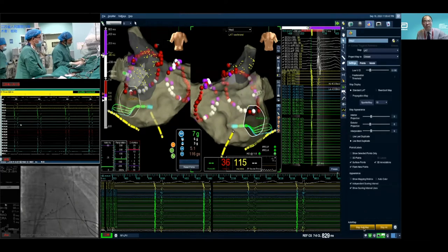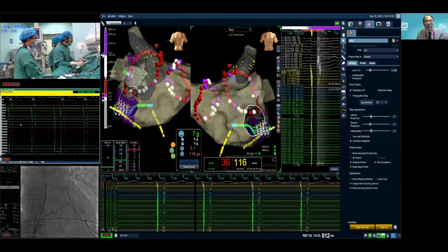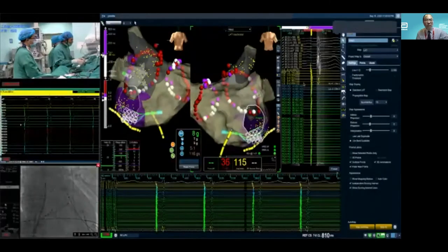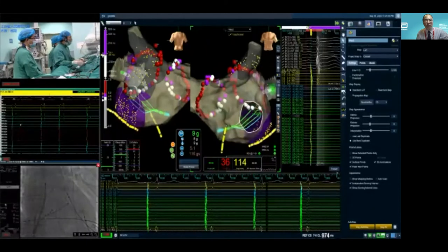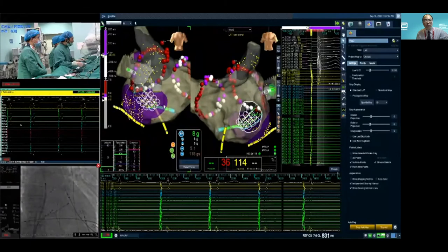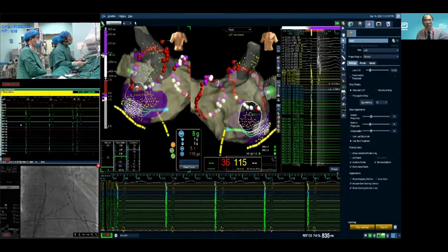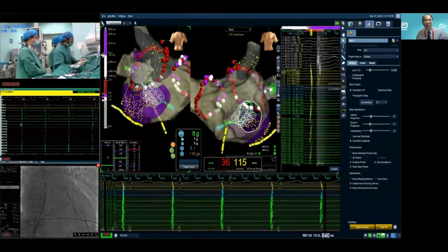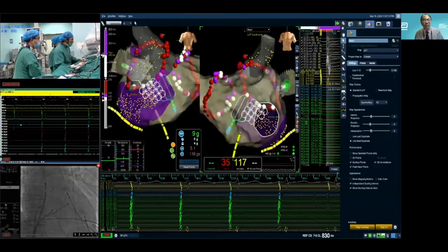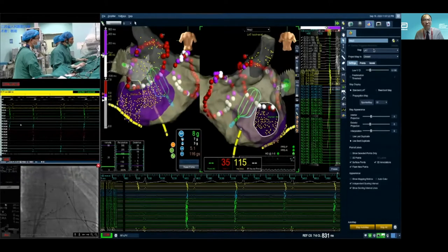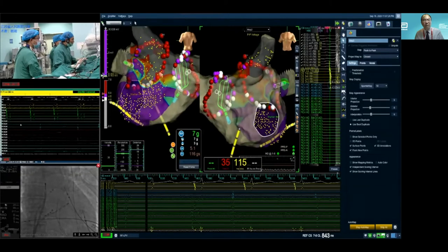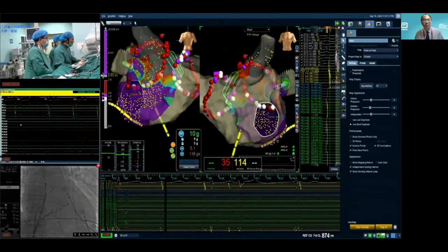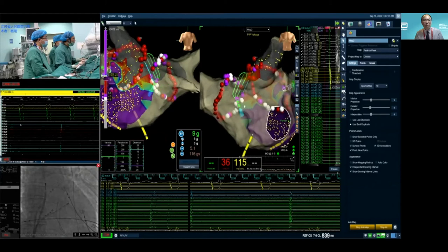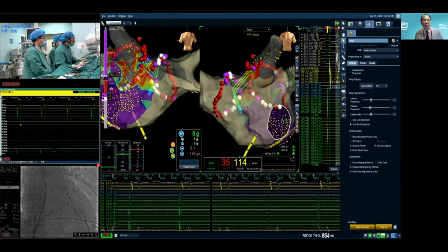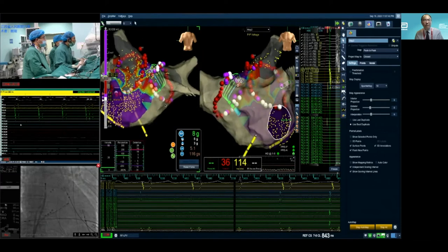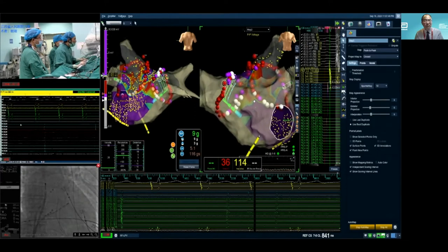The HD Grid catheter is very soft during manipulation in the left atrium. So we move the catheter very slowly, and we can collect more points. And we use the auto map function of the system. On the posterior wall, we will rotate the catheter clockwise to make the catheter tip contact with the posterior wall. That purple is correct. Now here is the posterior wall, and we can see the two circles are too close.